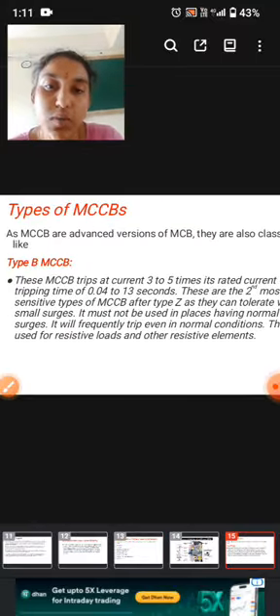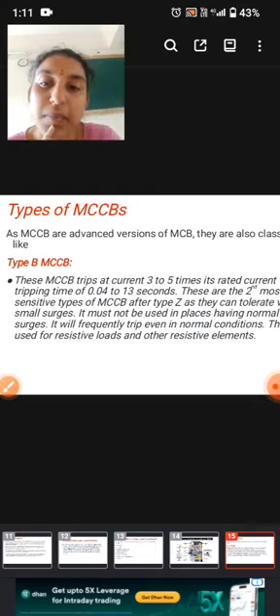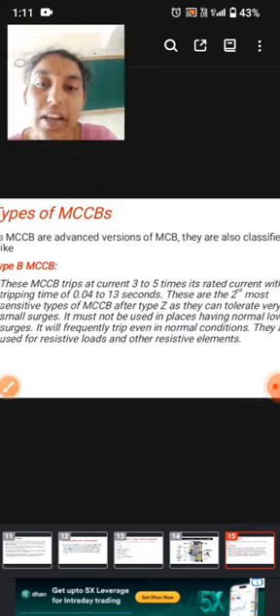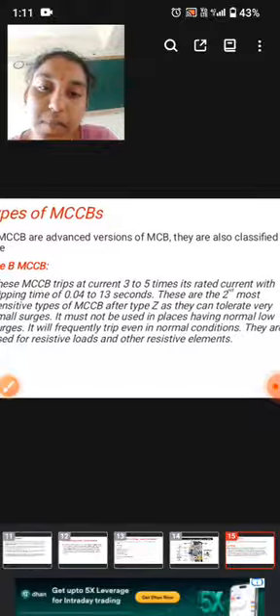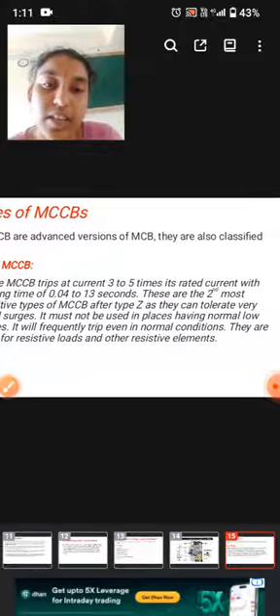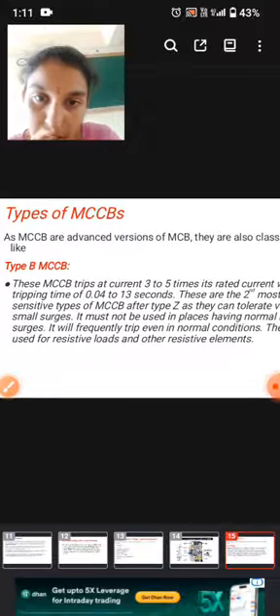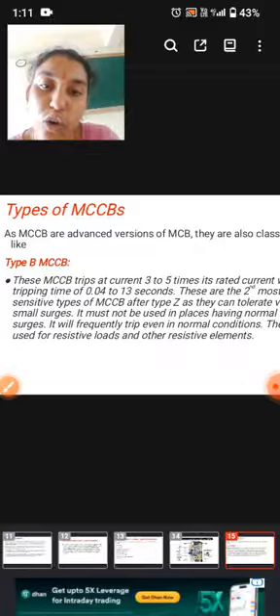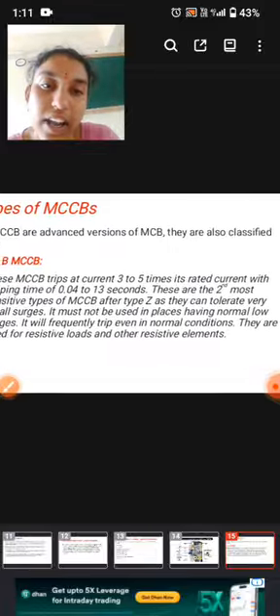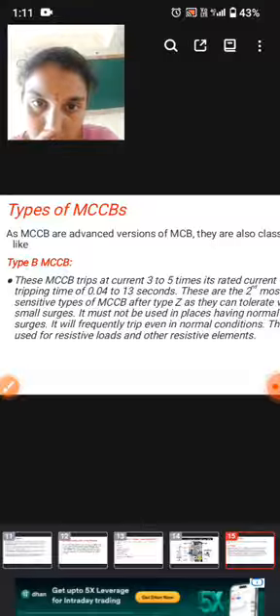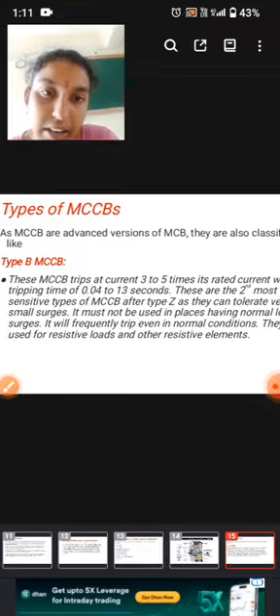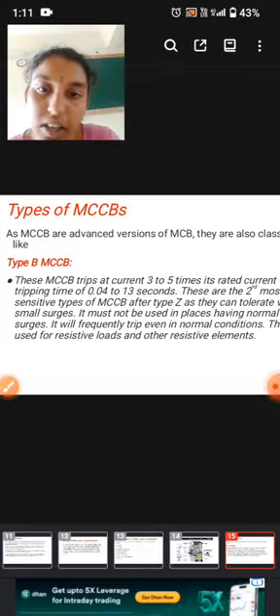Now we'll look at the types of MCCB. There are four types of MCCB, and the first is type B MCCB. These MCCBs trip at currents 3 to 5 times their rated current, with a tripping time of 0.04 to 13 seconds. They are the second most sensitive types of MCCB after type Z, as they can tolerate only very small surges. They must not be used in places with normal low surges.